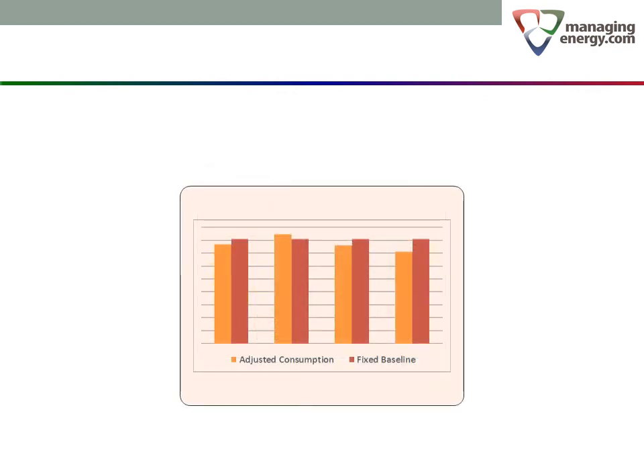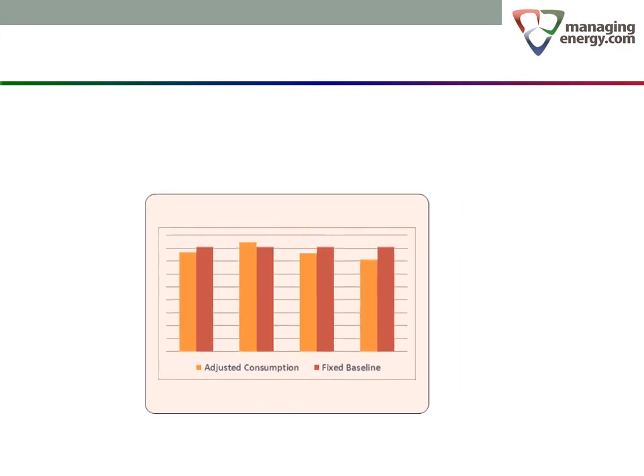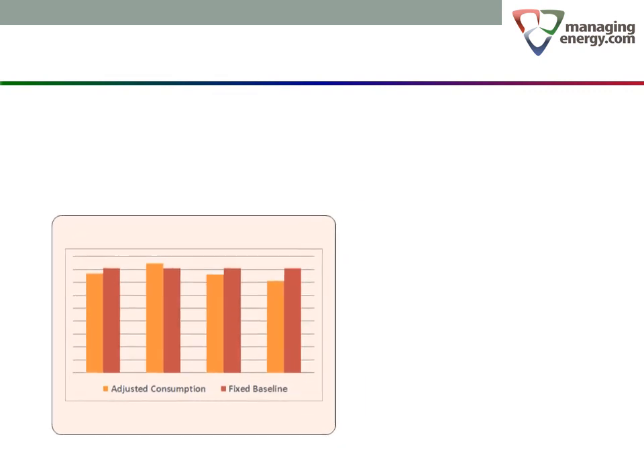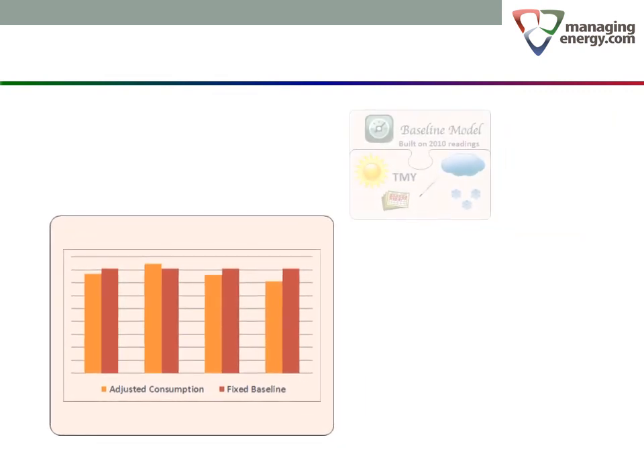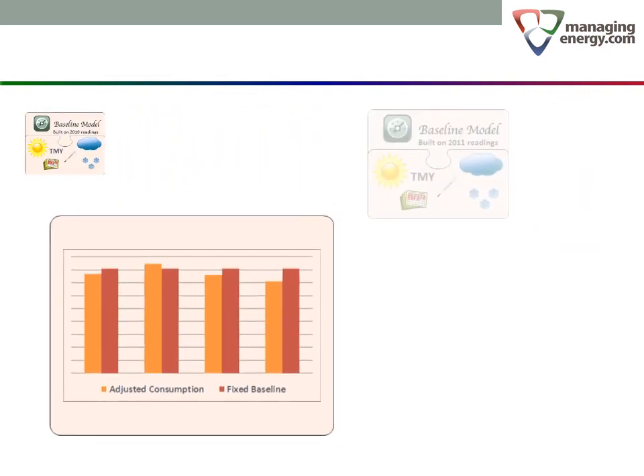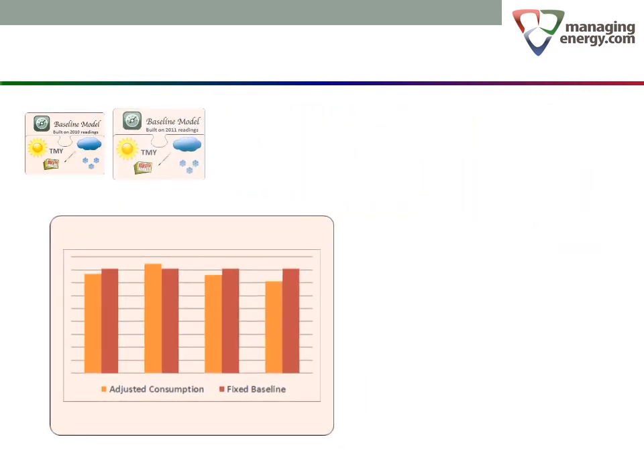Now we need to adjust the consumption in each year for weather differences. First, we create a model for each year. Remember that the model is a mathematical representation of how the consumption responds to weather. The process is exactly the same as producing a baseline model for a base year, except now we are doing it for every year in the comparison. Why do we do that? Because we are trying to describe energy performance in each year against weather.